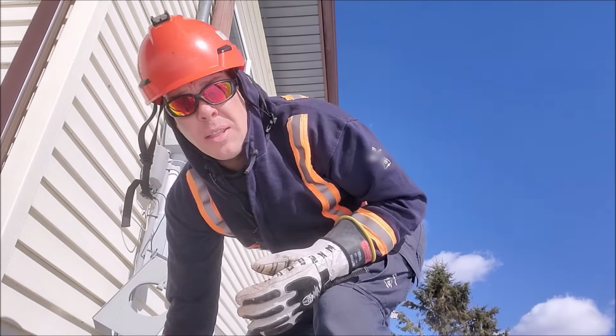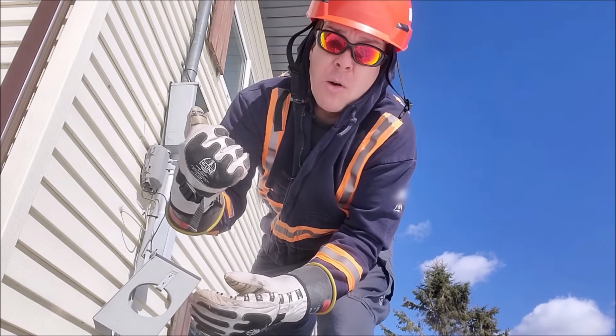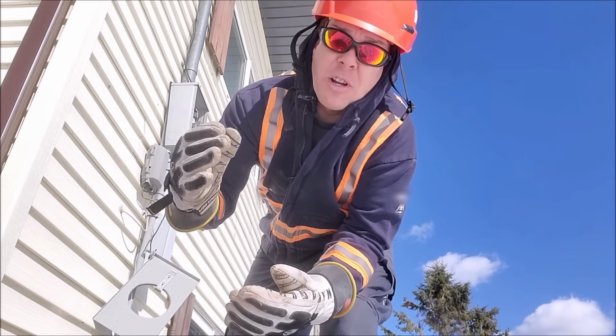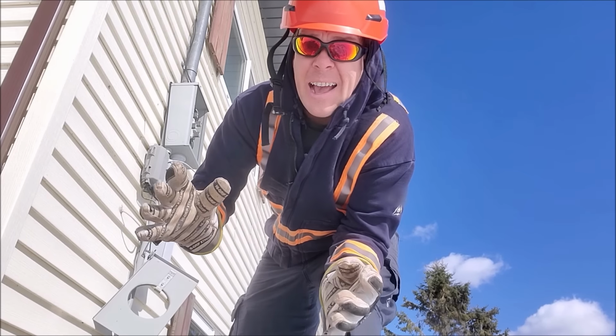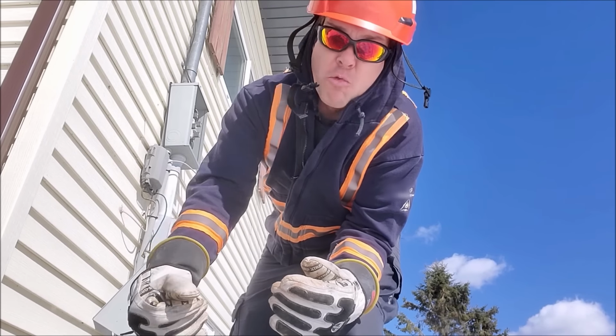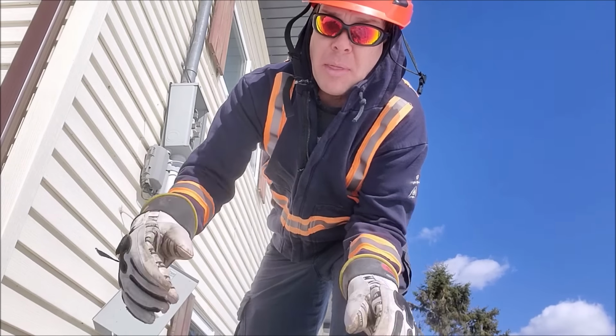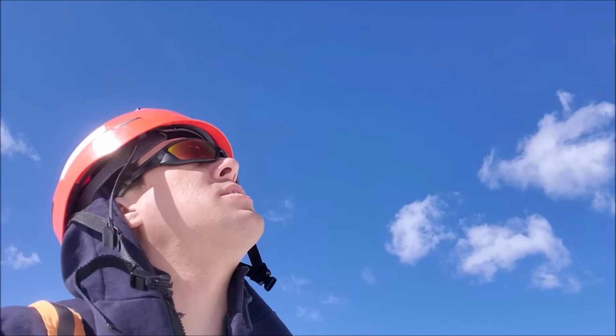Now it's very important that while we repair this neutral, we don't have the meter on unless we have the transformer open or the power shut off. The last thing we want is to have that voltage really skyrocket on one end and start burning things up in the house. Now usually when I start to troubleshoot the neutral, I'll just do a visual from the ground so I don't waste too much time getting ladders out and climbing poles and stuff.